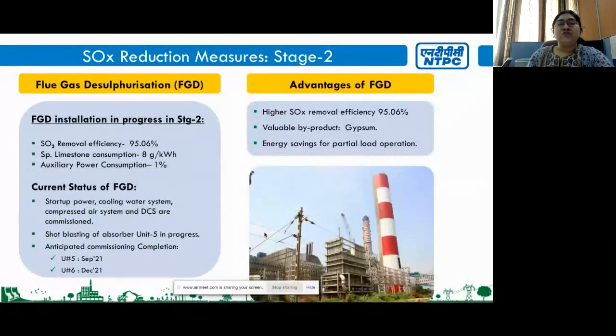And in stage 2, for SOx reduction, we have installed flue gas desulfurization system. This system is still under commissioning, and the commissioning will be completed for unit 5 in September 21 and for unit 6 in December 21. This system has a few advantages, like it has SOx removal efficiency of up to 95%, and we get a valuable byproduct, that is gypsum, that can be sold, and we get energy savings for part load operation.